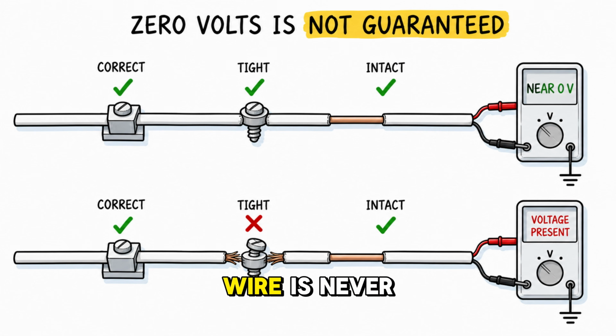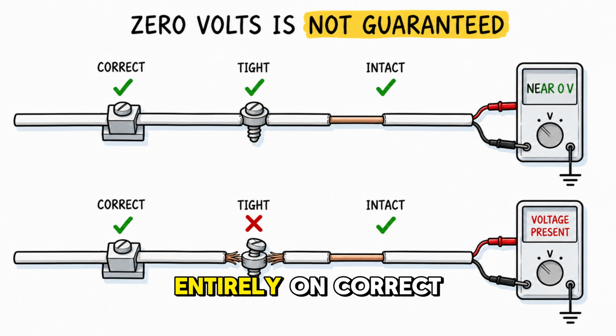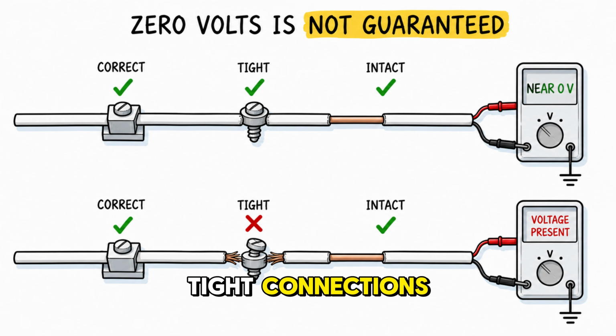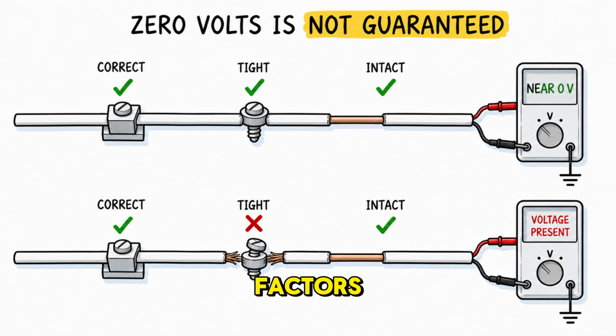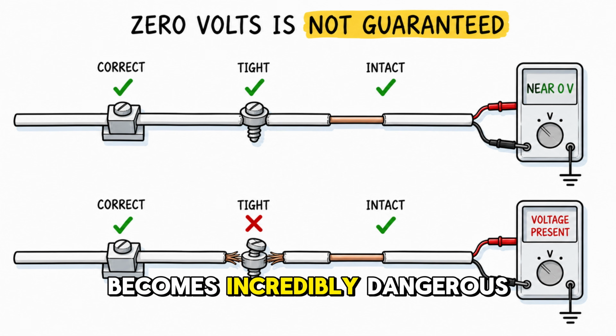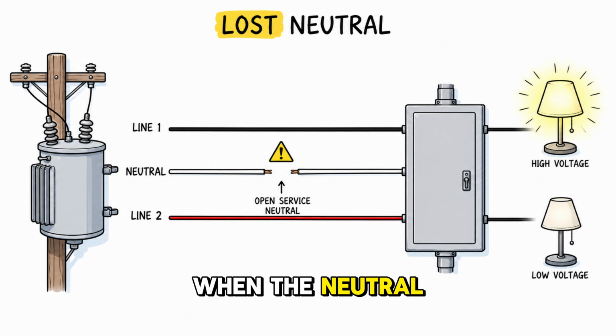0 volts on a neutral wire is never guaranteed. It is a temporary condition that depends entirely on correct installation, tight connections, and an intact copper path. Take away just one of those factors, and the neutral wire becomes incredibly dangerous. When the neutral wire breaks between the transformer and your service panel, the results are immediate and destructive. This is called a lost neutral or an open neutral condition, and it is one of the most dangerous faults in a residential electrical system.